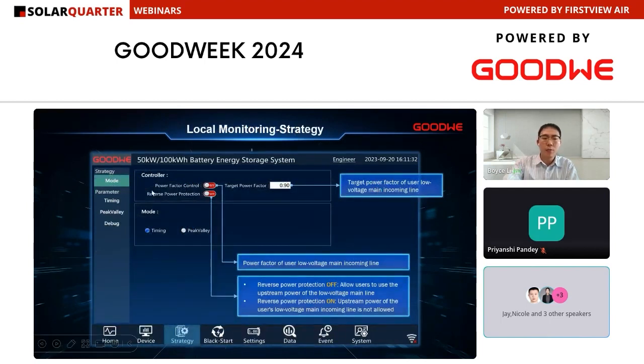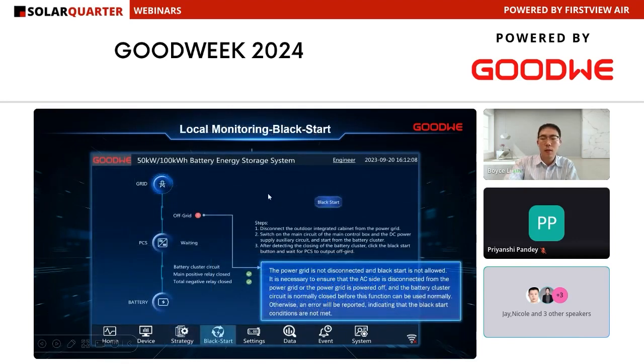We can also do some control for our BAC series, setting the mode and the power factor. We also have a black start function. During first commissioning, if there's no grid on site, after connecting the battery we can click black start and the system will start up off-grid.